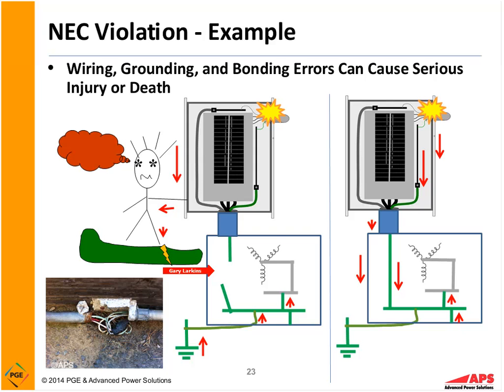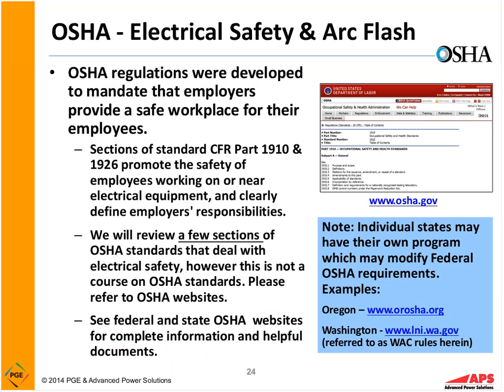Where on the right side here, we see that that conductor's in place. It's solid. It's in good shape. So it provides a good, solid fault current path for the current to go back. And if everything's installed properly and functioning properly, the breaker should trip within, let's say, a couple cycles for a molded case or an insulated case breaker, which helps prevent electrical injury or worse yet. Okay, so that was just a couple examples from the NEC, but it's very important. There are a lot more we could give.